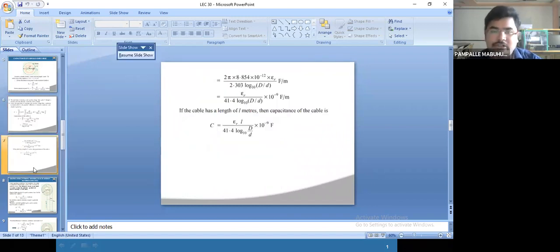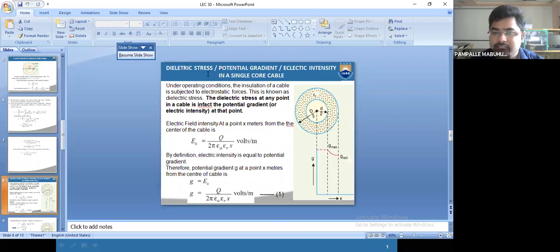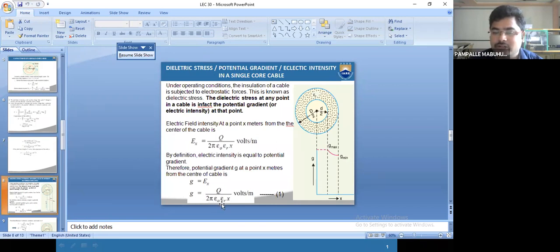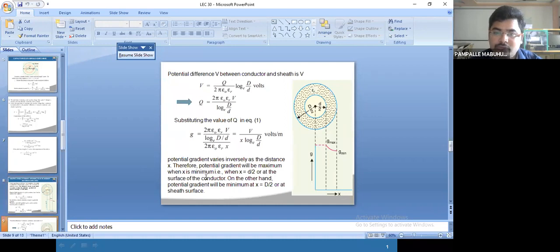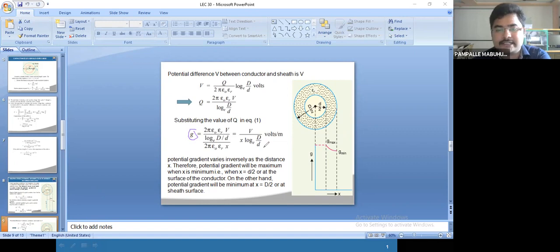We also derived the expression for calculating the dielectric stress, which is also called potential gradient. The potential gradient or dielectric stress is represented with small g. That g value is q / (2π·ε·x), where x is the distance from the center of the core. So g = V / (x · ln(D/d)).